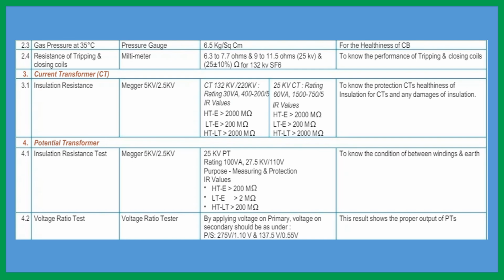Then current transformer. For the current transformer on the 132 kV or 220 kV side, the rating is 30 volt ampere, with ratios 400 or 200 by 5. Two ratios for the current transformer. IR values: HT to earth is 2000 megohm, LT to earth is 200 megohm, and HT to LT 2000 megohm. And on the 25 kV side, it is 60 volt ampere.